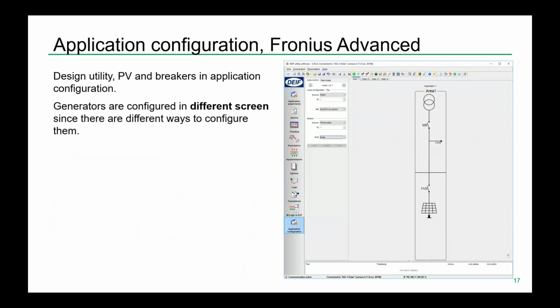Other questions we get are also about how we configure this. Application configuration, as we call it. You can see the picture of our programming tool, the utility software. This is a tool where you design the plant. And now for the advanced solution, I have a mains incomer, a mains breaker, the PV breaker, and then at the bottom you can see a symbol of some panels, but it is the inverter installation that you have there.